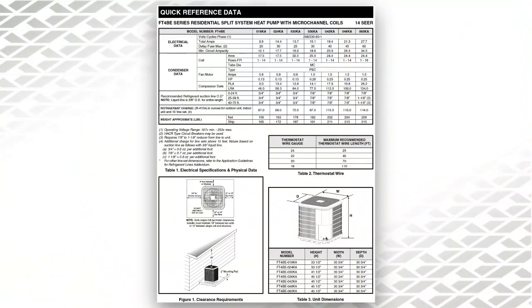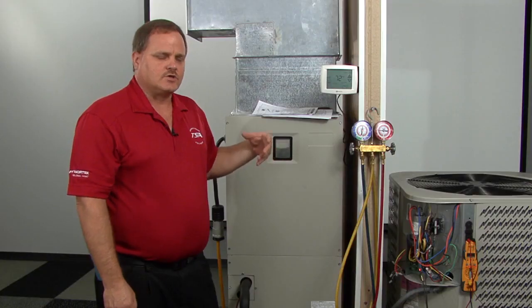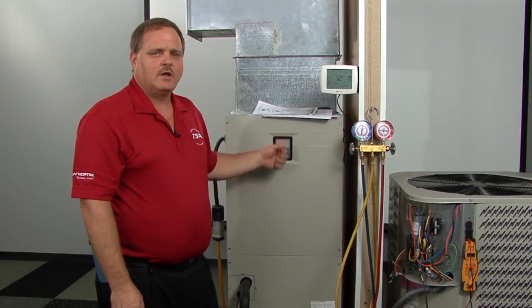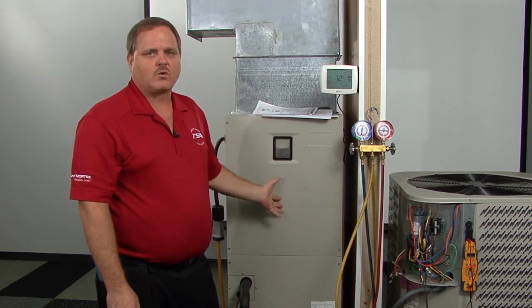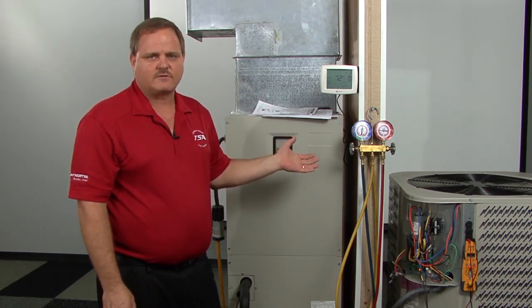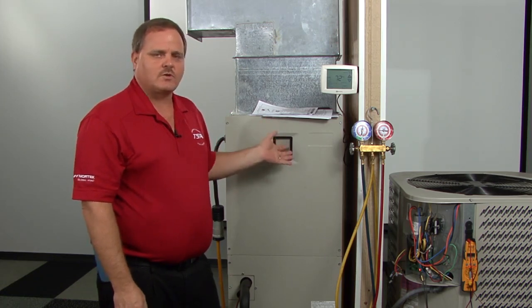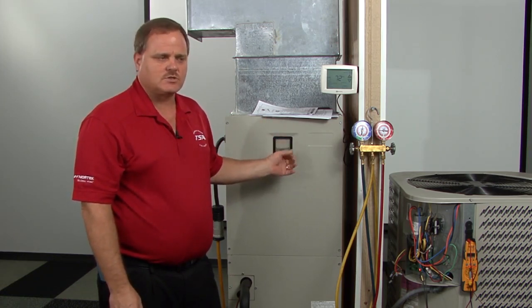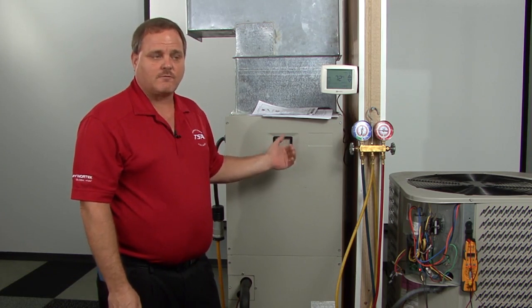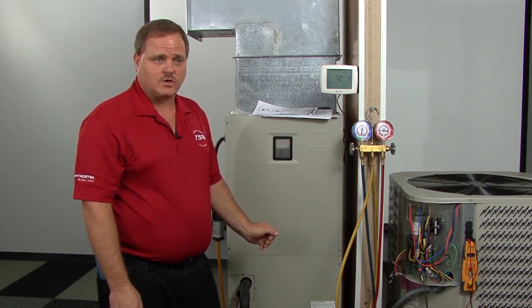Okay, so hopefully you've followed the quick reference data sheet that came with the outdoor unit, and that we've set this blower up inside, like I was talking about a minute ago, with the blower speed settings. Once you've done that, I would hope you're taking it one step further, and you're using a Magnehelic gauge or a digital manometer, and you are running just the blower inside. You don't even have to have the breaker on outside yet. Just running the blower, making sure that static pressure is within specifications, and that we're moving the appropriate CFM, referring back to the blower chart in the installation instructions.